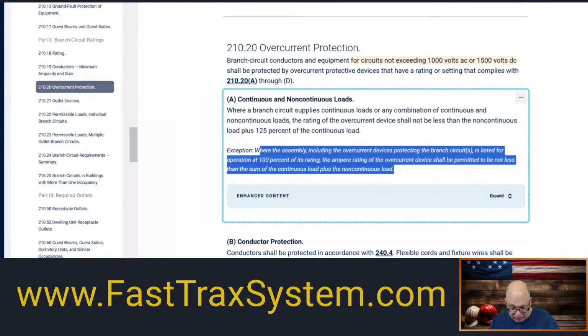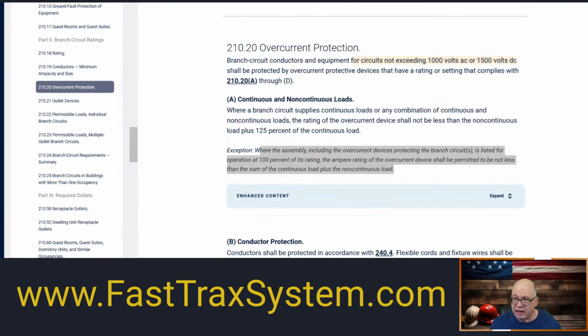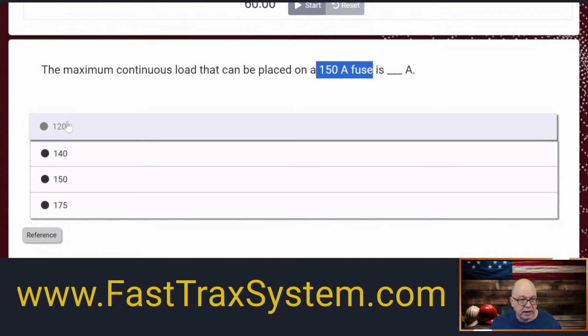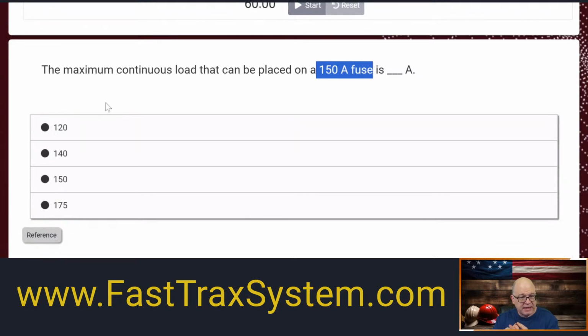So we're limited. We're going to take that 150 and multiply it by 80% or 0.80, because that's going to give us what? That's going to give us 120. That is one of the answers here, 120. Now we can check our work by taking the actual load, which is the continuous load. I always tell people also, remember, the load is the load. Just because we take something at 125% doesn't change what the load actually is. It's still 120 amps of load.